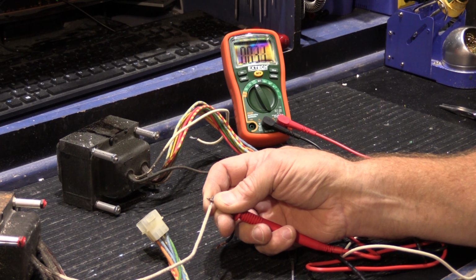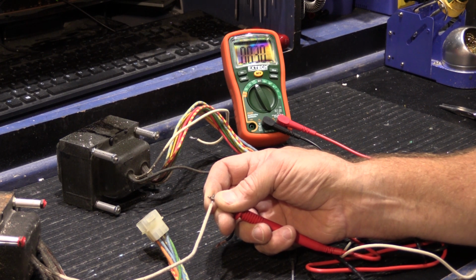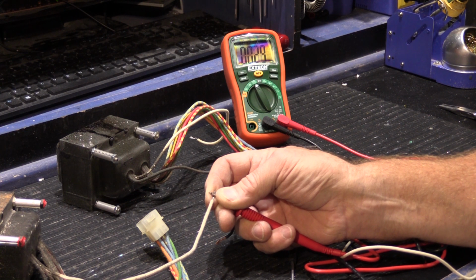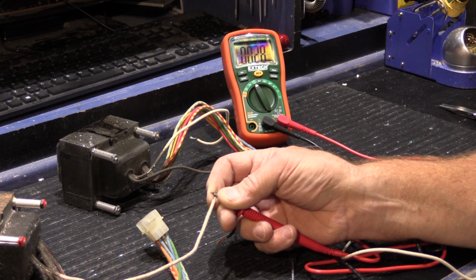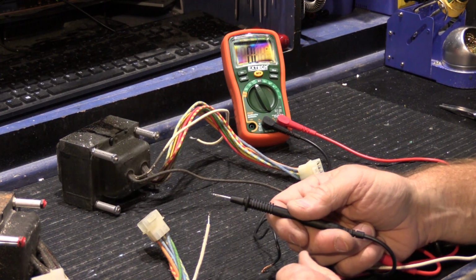We get about 3.1 ohms, which is very close to what the service manual says the resistance of the primary winding should be. I also verified that on a second good one that I have, my bench transformer, to make sure it was reasonably close, and they are.